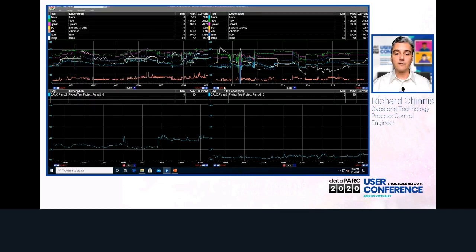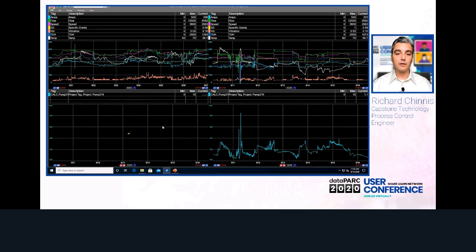Now I'm going to get rid of my D mod X filter and put the HT2N on the left-hand side. And we said that we wanted to evaluate on this time frame, so I'm going to drag my time frame down here. But what is it telling me? It's not telling me anything yet. There's another step that I need to do, which is to turn on limits. When you click that continue button to save your model in the system, it's not just creating these statistics tags, it's also creating the limits based on the data that you fed it.